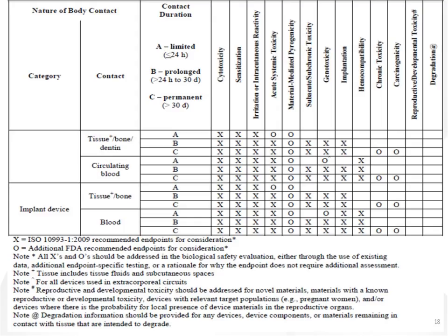Carcinogenicity testing can be very, very expensive and long. We're talking millions of dollars. It takes years to do. So not many medical device manufacturers perform that test. And in the past, it's kind of been one of those things that people just forget about. Well now, and we've actually seen this from the FDA, they're asking you to evaluate carcinogenicity. And you can't just use genotoxicity as an endpoint to evaluate carcinogenicity. You need to do a carcinogenicity evaluation. That does not mean testing, or else labs would have a lot more revenue. What that means is that we need to find a way to evaluate the carcinogenicity potential of the device. It could be material evaluation.